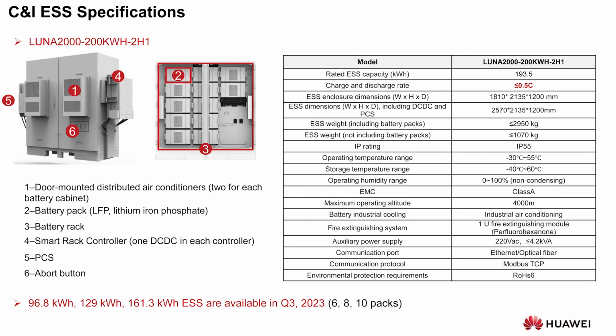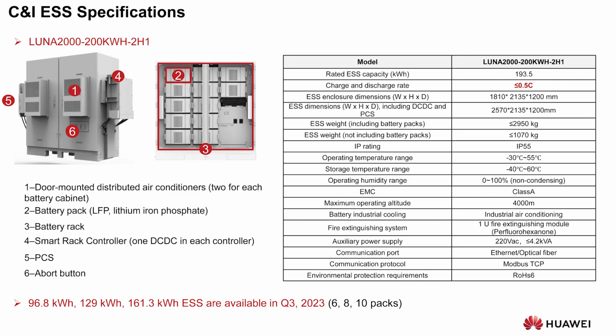Just to give you some specifics about the unit itself: number one here is your door-mounted distributed air conditioning. This is a commercial grade air conditioning. It does not have any condensation. This is what you need for your batteries. You've got your battery packs, which are inside here. Each battery pack is a lithium iron phosphate compound, 16.13 kilowatt hours. Then the entire container, we call it a battery rack. You've got your smart rack controller on the side here, which is number 4. Number 5, you won't see on the side here, it's a 100 kilowatt PCS. Basically, it's a charge controller that charges the battery in DC and discharges the battery from DC and then converts it to AC. And then you also have a safety button here, so you can abort it.